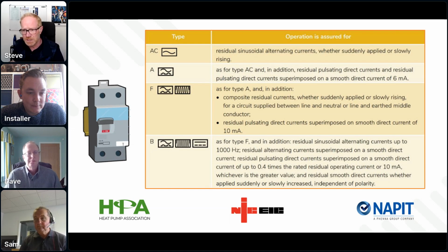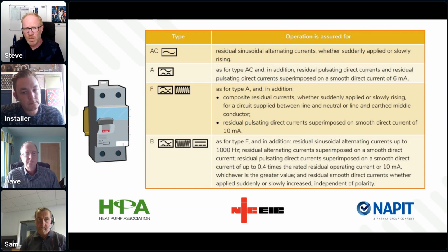It's not outside of BS 7671. It is a normal type B, and the way that's been done, so it's not like a B plus, is it's been manufactured, or sorry, engineered would probably be the better word, where they haven't altered any of the actual electronics, the way it works, to make it a new product standard. They've been very clever. What they've done is they've just, the component parts and the quality within those component parts, are able to increase those certain characteristics.